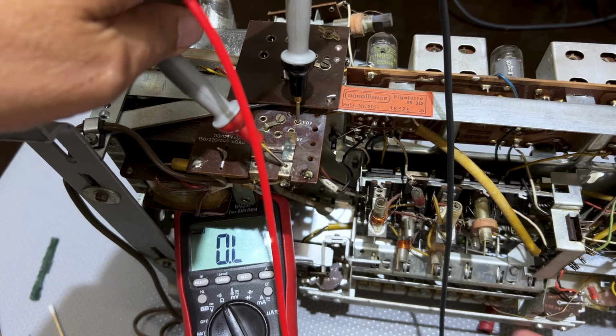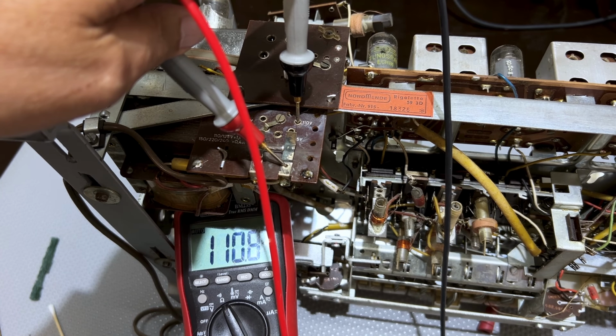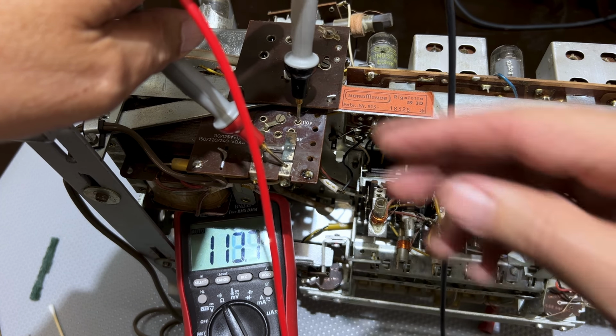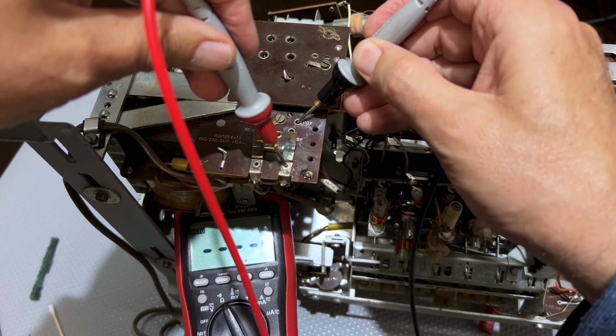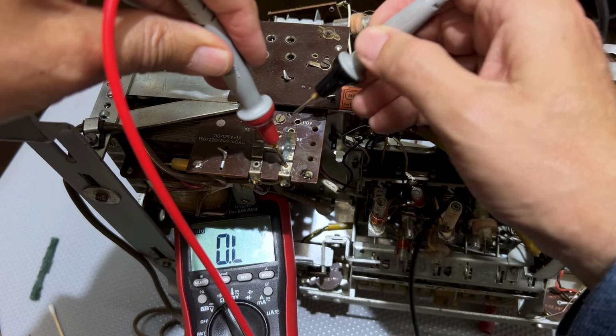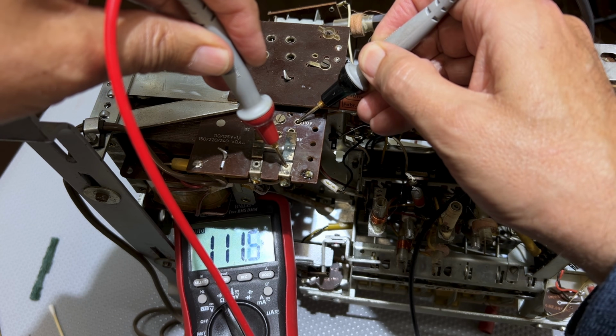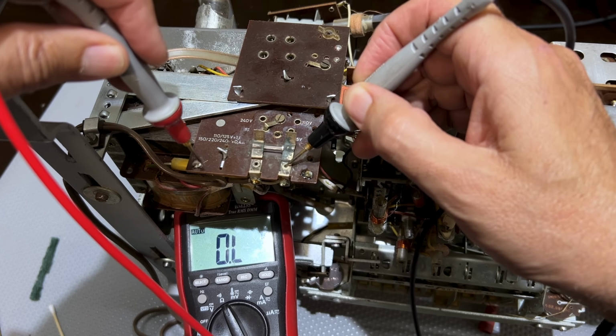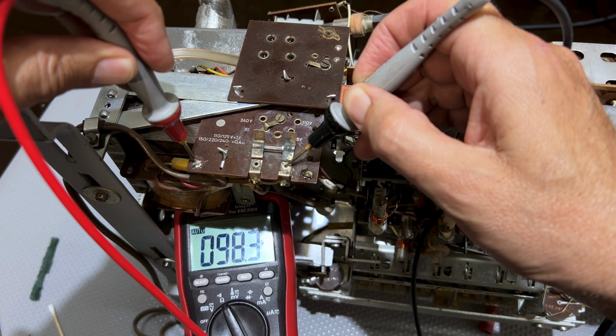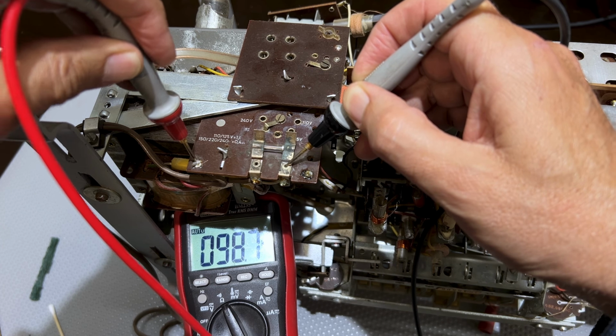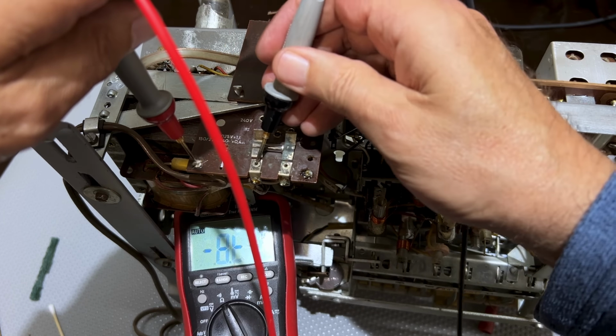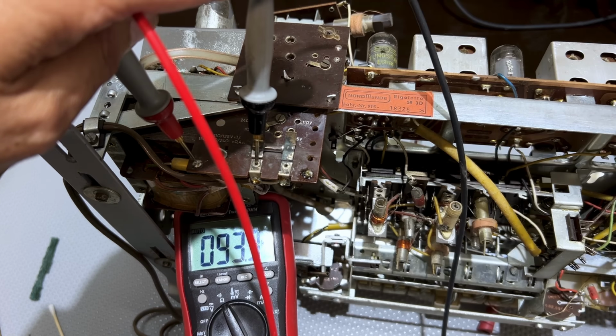And let's put it on. Now we're getting 100 ohms. This is giving us a reading through the switch. The switch is dirty, and that's why we're not getting a reading, or getting a different reading. Here we've got 98K. This thing's giving us strange readings because the switch is not clean.